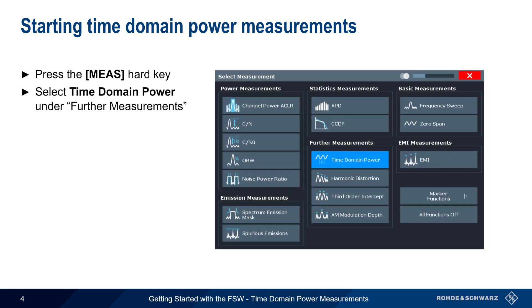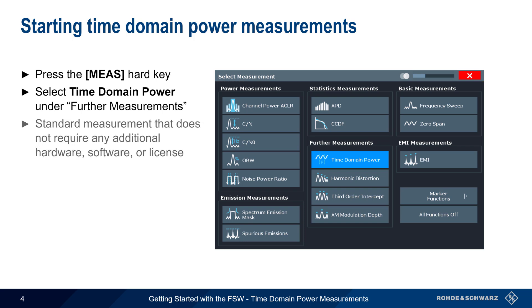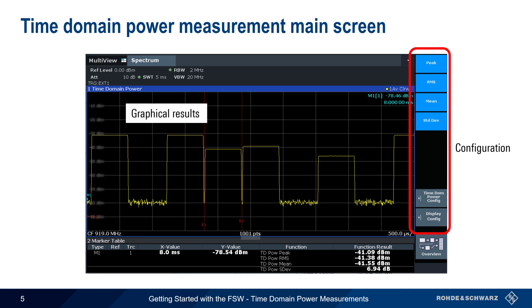To start a time domain power measurement on the FSW, press the Measure hard key, and then select Time Domain Power from the list of further measurements. This is a standard spectrum measurement and does not require any additional hardware, software, or license code. This is the main Time Domain Power measurement screen. Configuration settings are accessed via the buttons on the right. The default view shows both graphical results as well as numerical results beneath them.